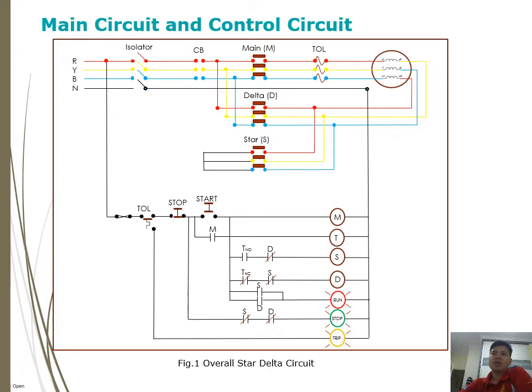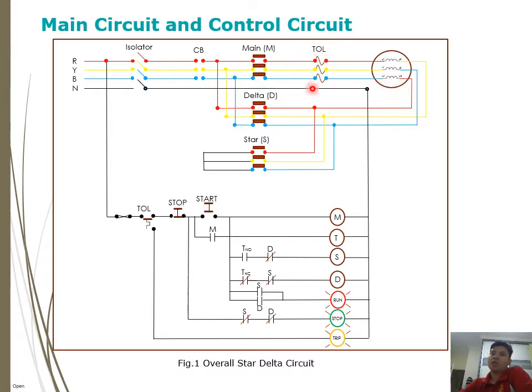This is the main circuit and the control circuit for the star delta motor connection. The power circuit is indicated by red, yellow, blue, and neutral — a three-phase power supply going to the motor — and also a control circuit for the motor start/stop or tripping control. There are three contactors being used: a main contactor, a delta contactor, and a star contactor. The motor winding has six leads — for example, R1, R2 for the red phase, Y1, Y2 for yellow, and B1, B2 for blue — plus a thermal overload relay.